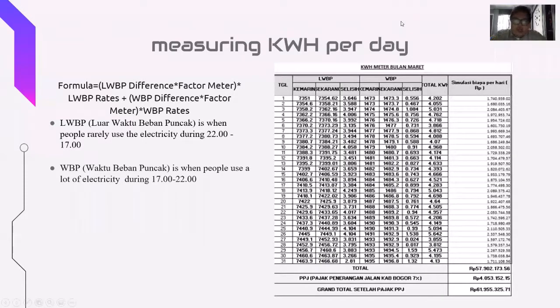And then there is measuring kWh per day. They keep tabs on how much electricity they actually use per day, and then they calculate it so it matches the bills from PLN. The formula is basically LWBP, luar waktu beban puncak, times the meter factor times the LWBP rate, plus the WBP, waktu beban puncak, difference times the meter factor times the WBP rate.